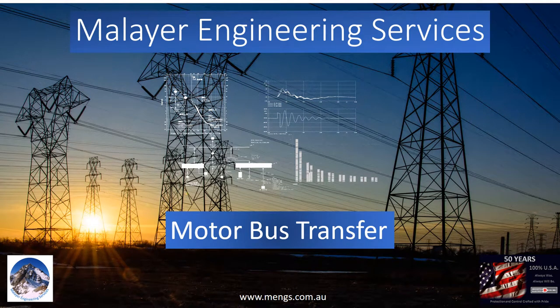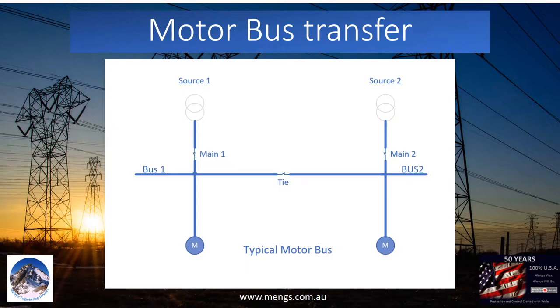In this video, we discuss various types of motor bus transfer. In most industrial applications, to provide higher reliability, any motor bus is supplied from at least two sources of supply. The main-tie-main is the typical configuration for motor buses. Any source of supply plays the role of a redundant source for another side of the bus.